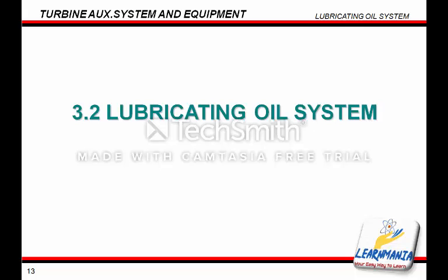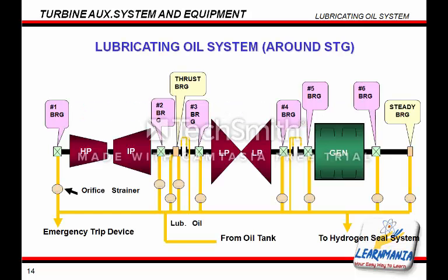Next we will explain the lubricating oil system. This is an outline of the lubricating oil system for the turbine and generator equipment. The lubricating oil system supplies oil to all bearings of the turbine and generator, the coupling, and the hydrogen seal equipment. The orifice strainer shown on the left-hand side of the figure regulates the amount of oil supplied to each bearing.